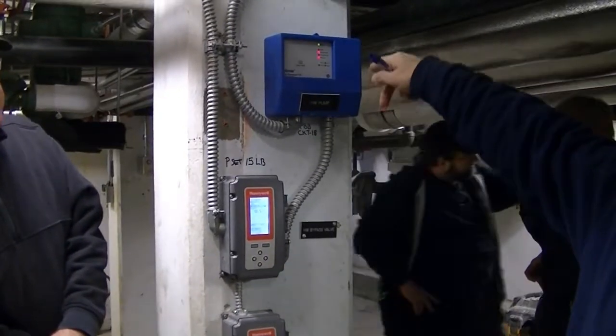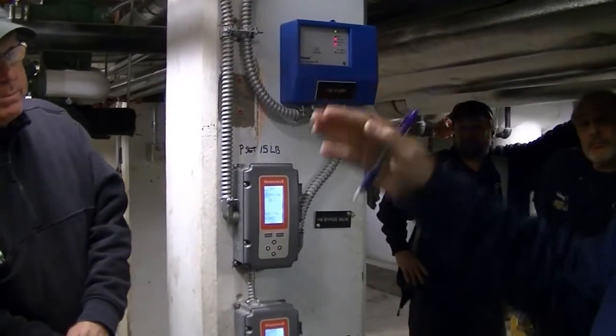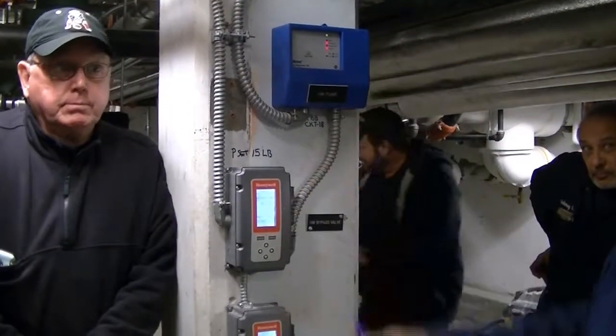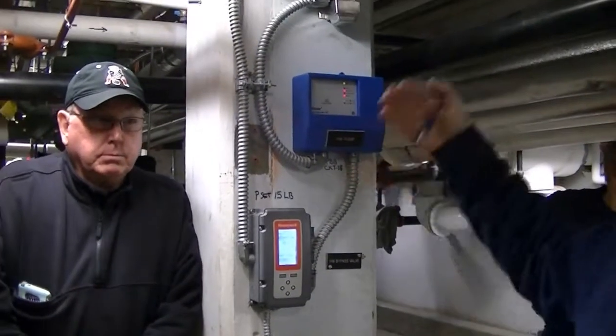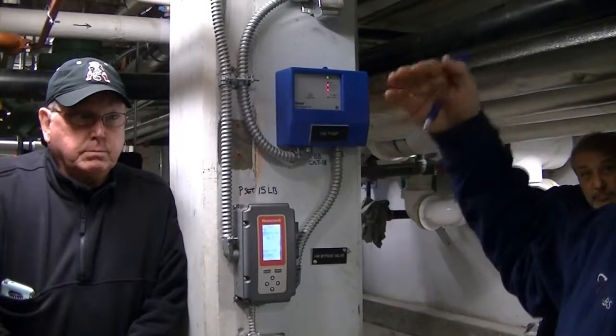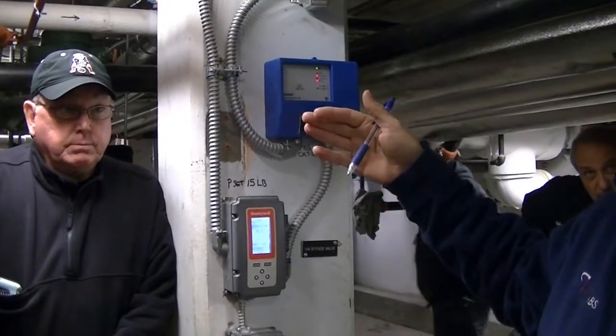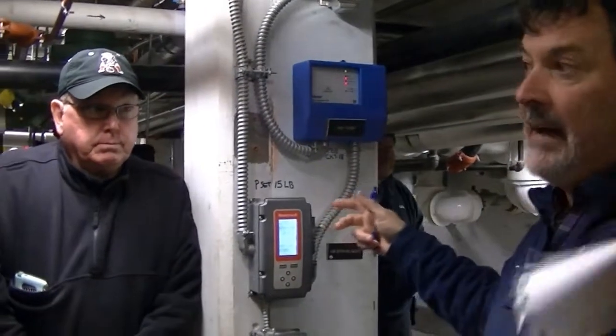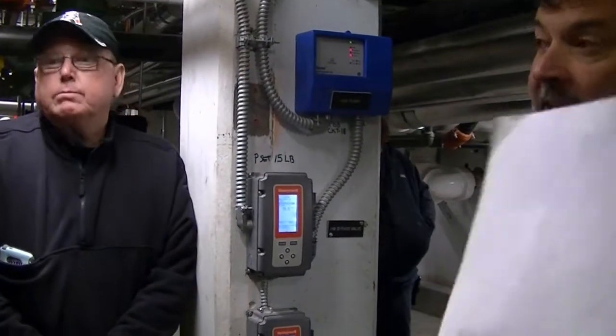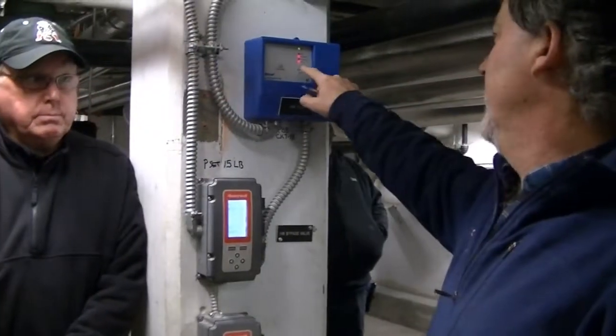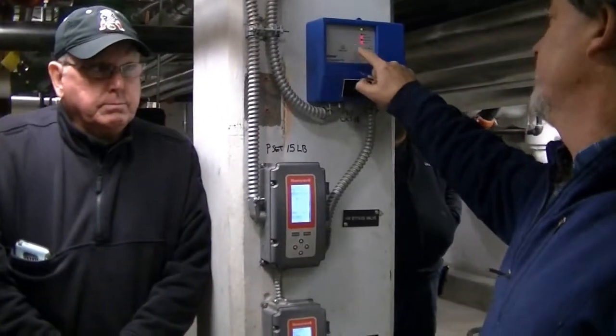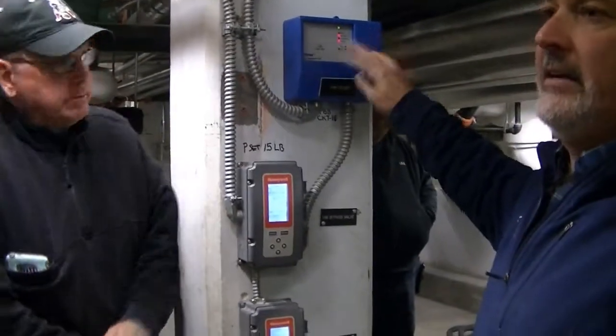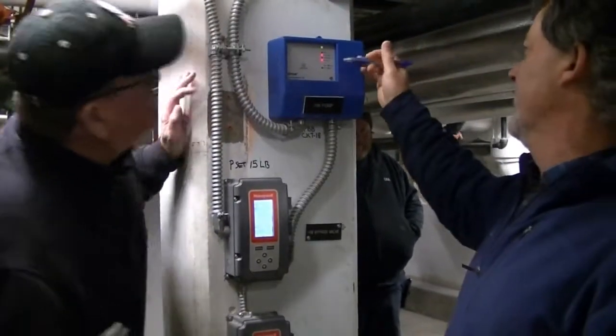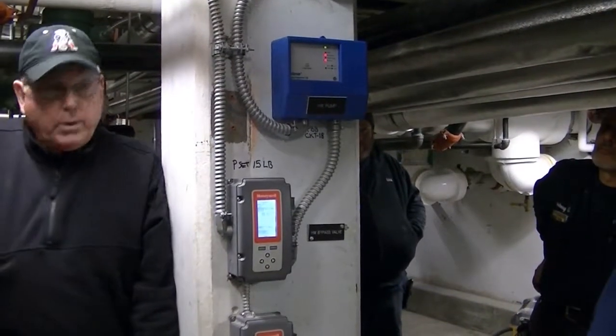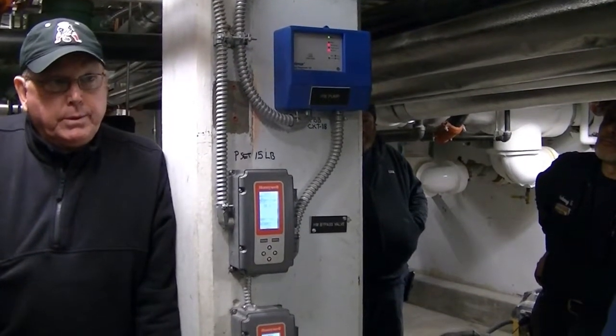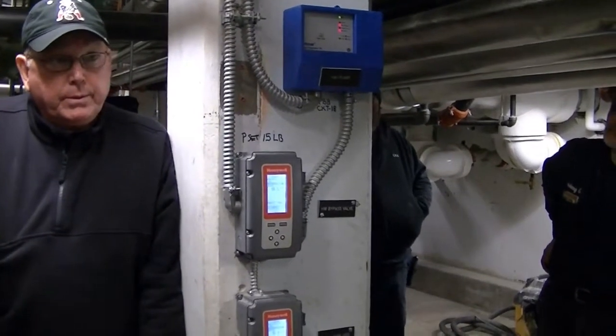Being a lead-lag system, anytime it's asking for the pumps to run and that flow switch isn't made, it's going to wait 30 seconds, then say we've got a problem. At that point, it's going to send a stop to the lead pump and start the other one, and you'll get an alarm light. I don't think this has any kind of annunciation feature. An alarm light will come on, and I'll demonstrate that. Basically, it's telling you there's a problem.